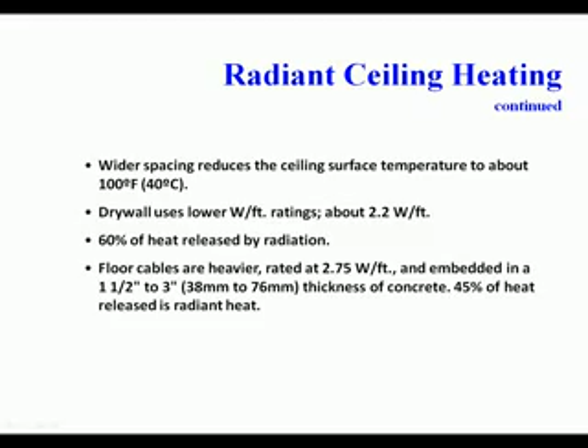It heats the ceiling surface to about 120 degrees Fahrenheit on 1.5 inch centers. Wider spacing reduces the ceiling surface temperature to about 100 degrees. Drywall uses a lower wattage per square foot, about 2.2 watts per foot, and 60% of the heat is released by radiation. Floor cables are much heavier. They're rated at 2.7 watts per foot, and 45% of the radiant heat is released.